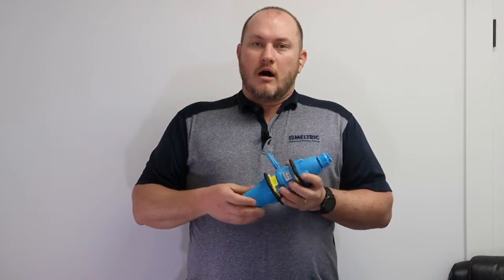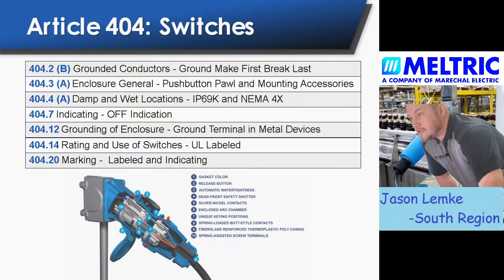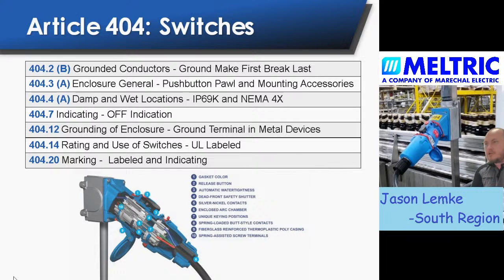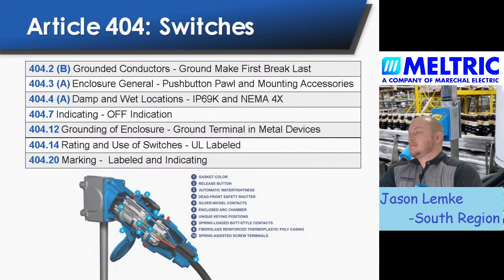Why do I want to do that? Because in all of these different applications in the National Electric Code, you have disconnecting means listed out. So for example, maybe we'll be talking about welders in a minute. In the welders section of the National Electric Code, they will reference disconnecting means, and they will put some critical features of what is required of the disconnecting means for that application. So when I went through the National Electric Code and looked at all of the applications that refer to a disconnecting means, I was able to find a couple of places that reference some of the key things that are required of a disconnecting means.